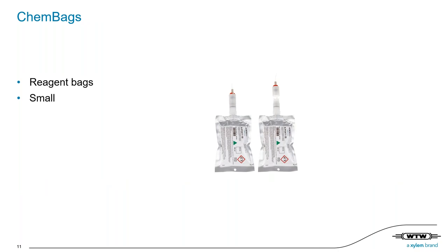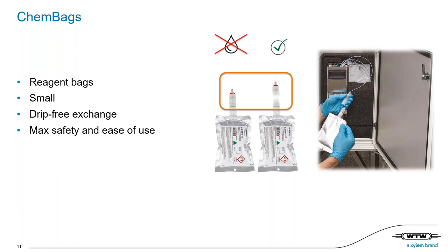For our new analyzer platform, we're using, instead of conventional reagent containers, bags to hold the chemical solution. With a total volume lower than 200 milliliters, they can be easily stored and transported worldwide. With a unique connector specifically designed for the new analyzer, the reagents can be exchanged easily and error-free. The connector is automatically opened and closed so that you never get in contact with the chemicals and you don't have to worry about spilling solution bottles. So maximum safety for the customer and you is given.